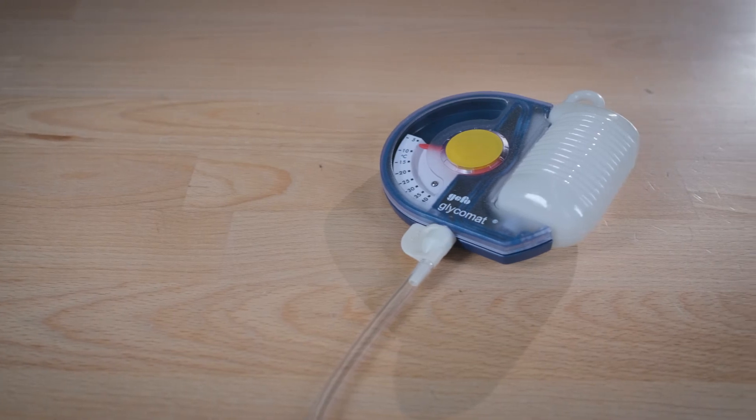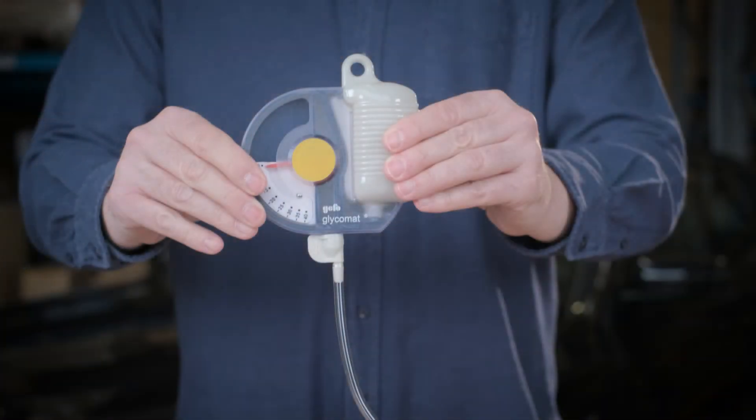With our gefo glycomat, we measured the concentration of antifreeze and water mixtures. This density measurement displays the frost protection — that is to say, the ice flake point on the scale.